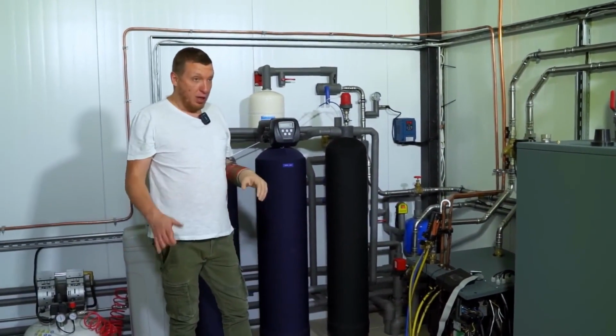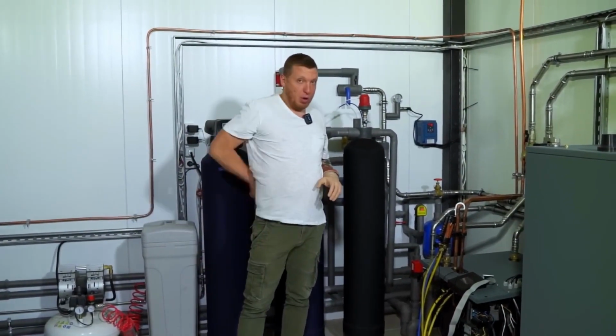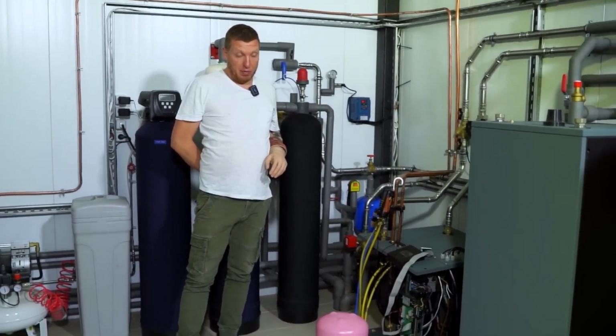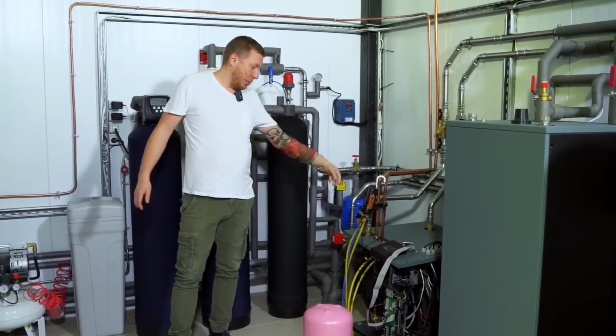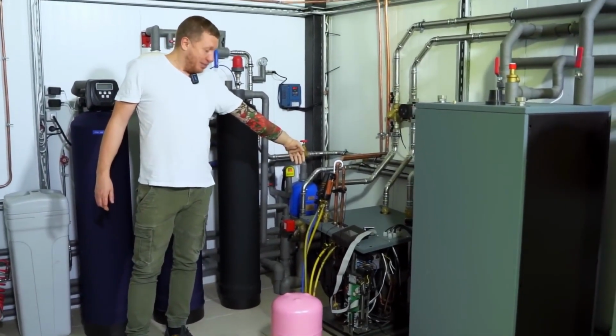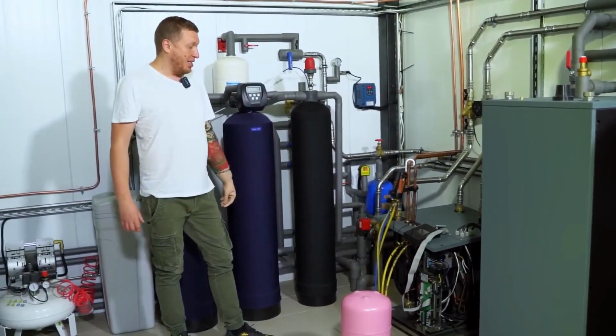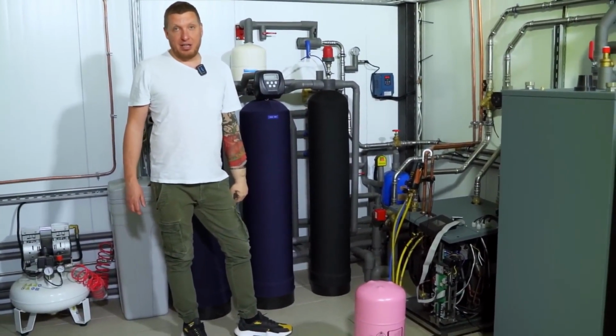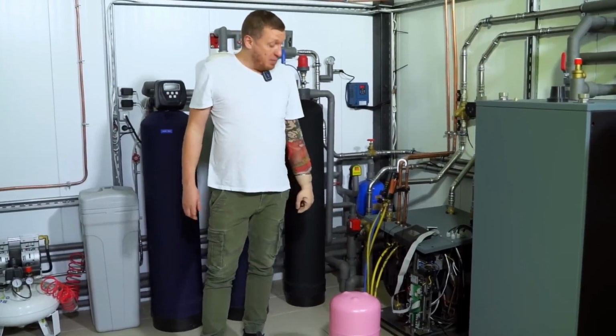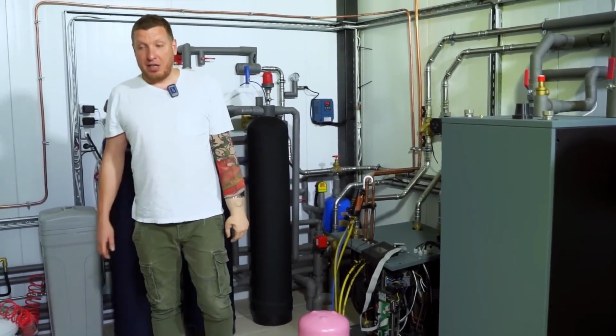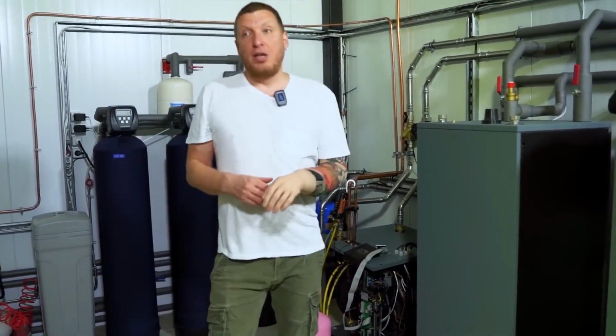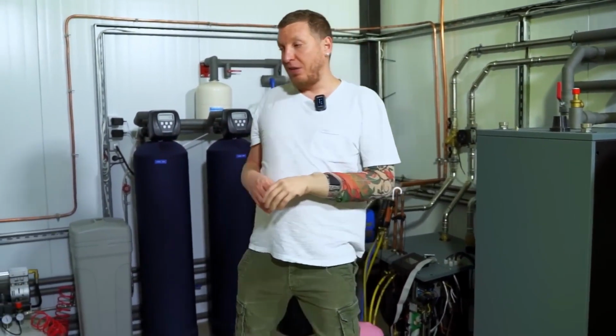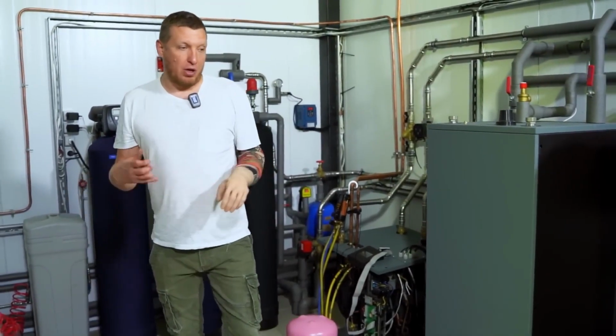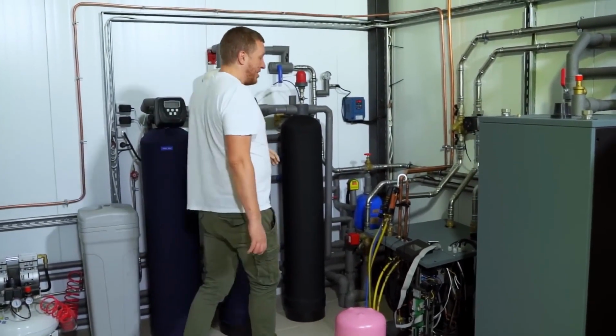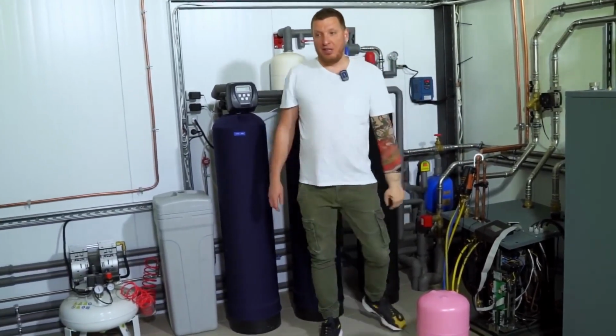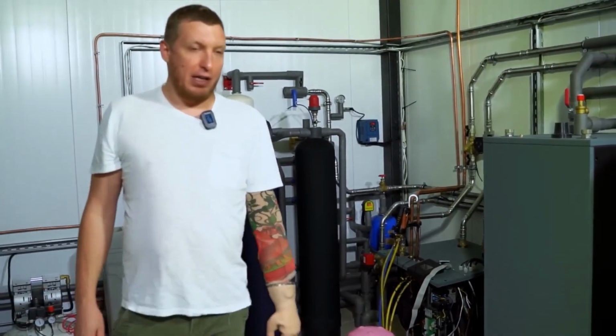Right now the circuit isn't fully charged. There's not enough refrigerant. We're going to add refrigerant now and check to make sure the parameters are correct. We have a special station, a manometric test. I like how it's connected. Now we'll adjust it so that we have the correct condensation and evaporation temperatures. And why do we use an inverter compressor? Since our load is variable, some parts of the room may be closed, others open. The compressor needs to reduce its speed so it doesn't max out. We control the compressor speed by the temperature of the return line in the refrigerant circuit. We set it to about 30 degrees and that's fine.